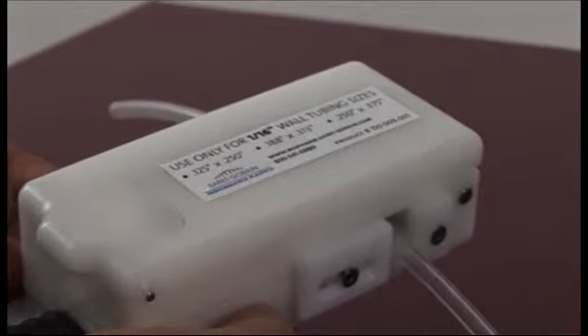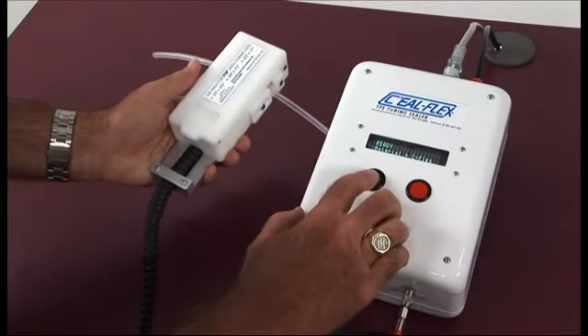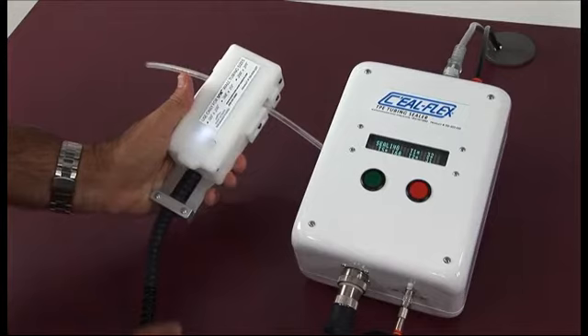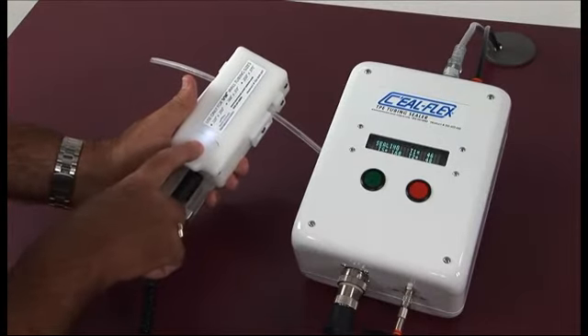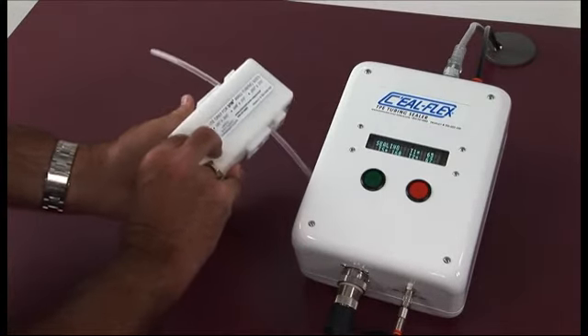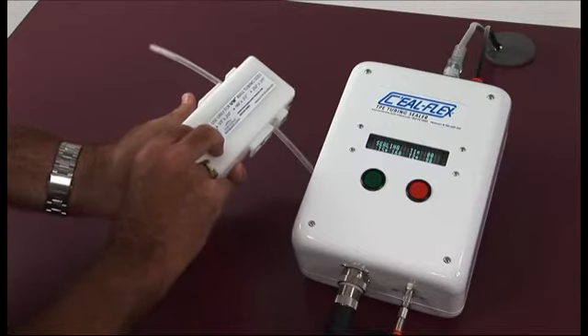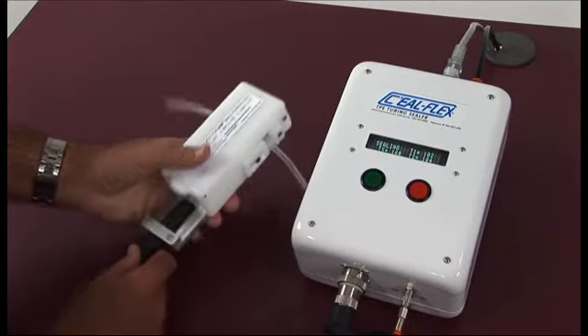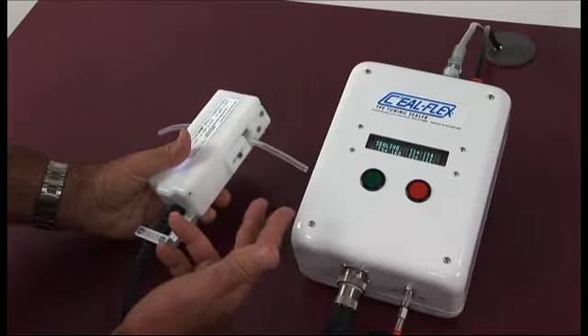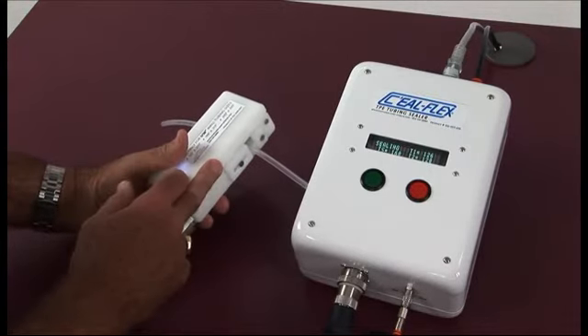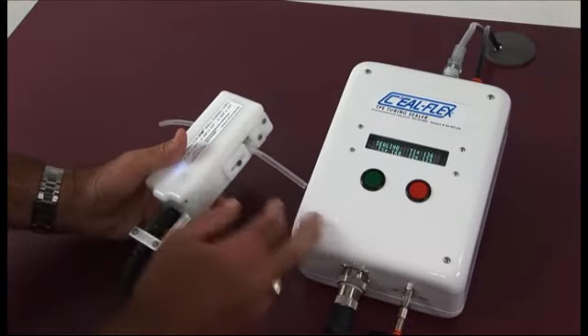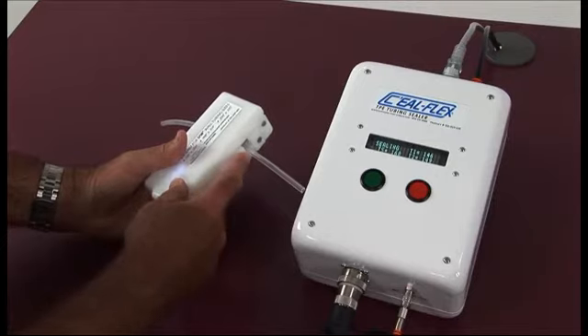Close the lid until it clicks, and press the green button on the base unit. You'll see a light come on in the head and the device. The head locks and will not open during the seal time. The seal time varies depending on the size of the tubing, ranging from about 50 seconds on the 1/8 by 1/4 up to roughly 3 minutes on the 1/2 by 3/4.